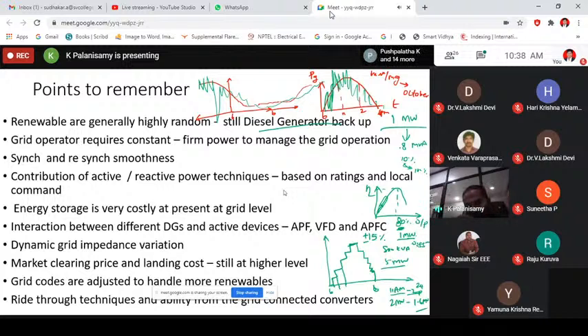But voltage is not so. When I measure the voltage here within my campus, maybe in a main building, it may be a different value, and if it goes to another building, maybe half a kilometer or one kilometer away, that will have a different voltage. So voltage is not a global variable. So if my inverter is working, let us say ride-through, for example, if the grid is facing a voltage issue, low voltage or over voltage, being an active converter, I can regulate the system voltage by adjusting the reactive power.